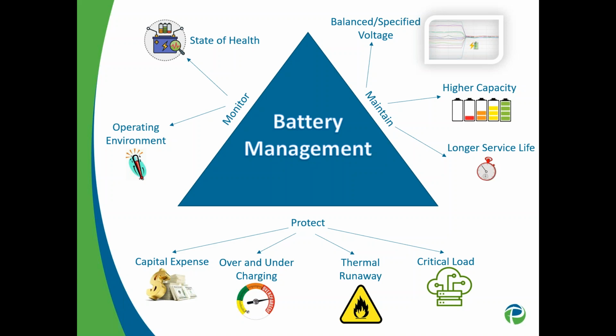A lot of battery monitors get a lot of over and undercharging voltage alarms, and there's really nothing you can do about it when you're just monitoring. It'll kind of alert you. A battery management system will see those over/under voltages and make the necessary corrections to keep it in balance, so you're not getting those nuisance alarms. A lot of times when that happens, your battery monitor turns into a boat anchor, and nobody wants to respond to every little thing that gets pushed out.